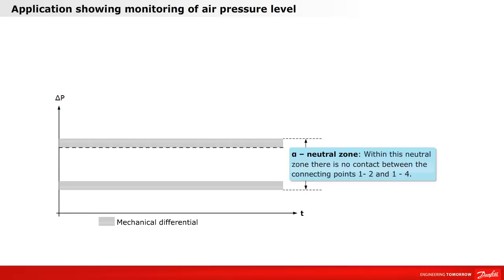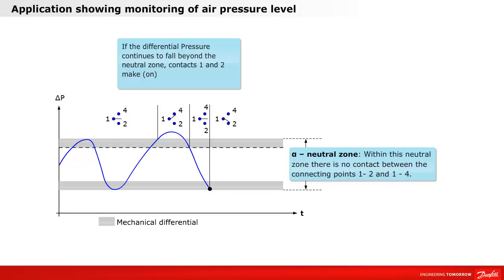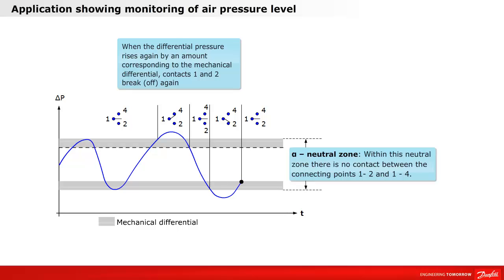Let's take a look at the contact function for a pressure switch and a differential pressure switch with a neutral zone. Within the neutral zone, there is no contact between connecting points 1 and 2, and 1 and 4. If the differential pressure rises above the neutral zone, contacts 1 and 4 make. If the differential pressure falls by the mechanical differential, which is fixed in the unit, contacts 1 and 4 break. If the differential pressure continues to fall beyond the neutral zone, contacts 1 and 2 make. When the differential pressure rises again by an amount corresponding to the mechanical differential, contacts 1 and 2 break again.